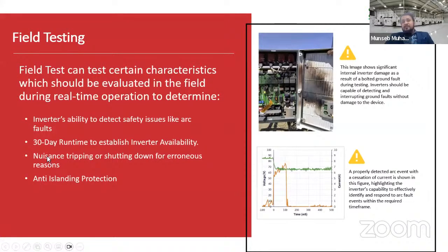And then you do the 30 days runtime to establish the inverter availability. This is very important for the financial modeling for any PV developer, to know the inverter availability for the nuisance tripping or shutdown for erroneous reasons. And then you can check the actual operation of the inverter for anti-island protection.